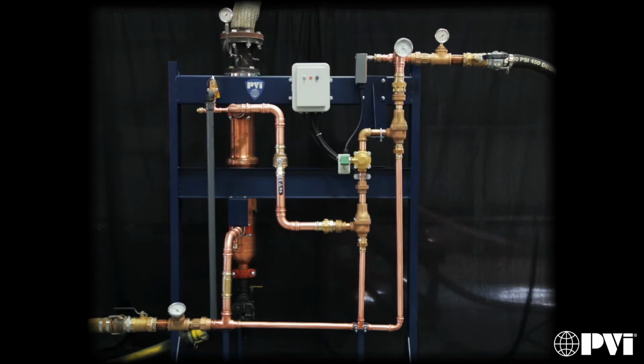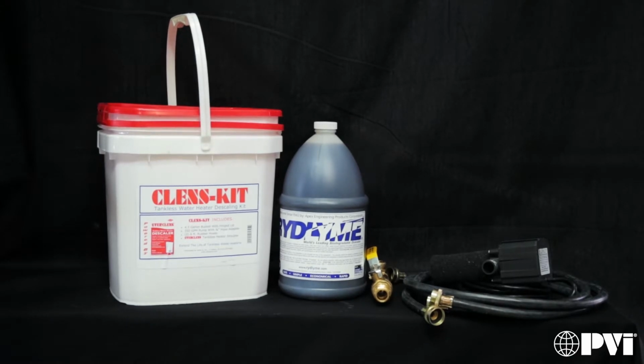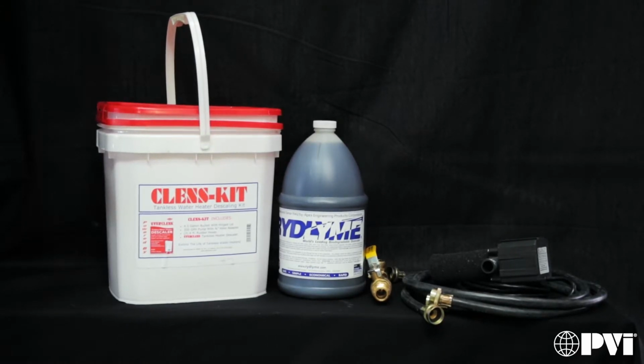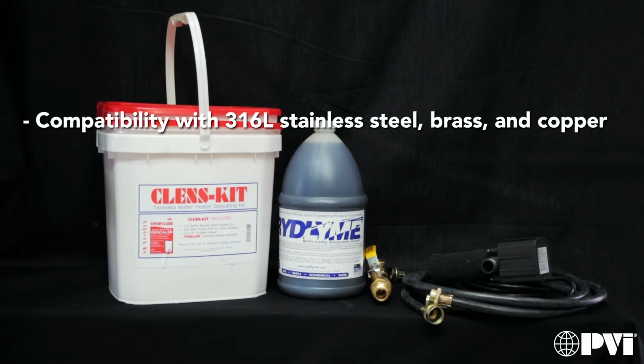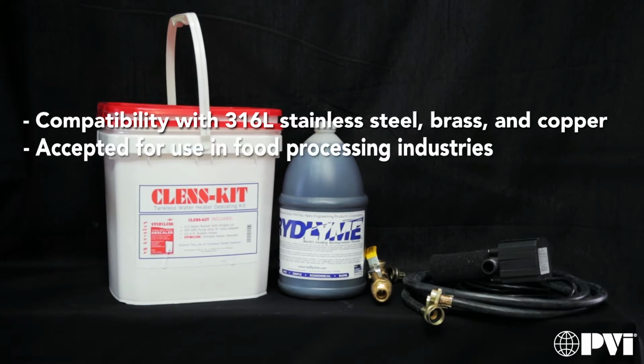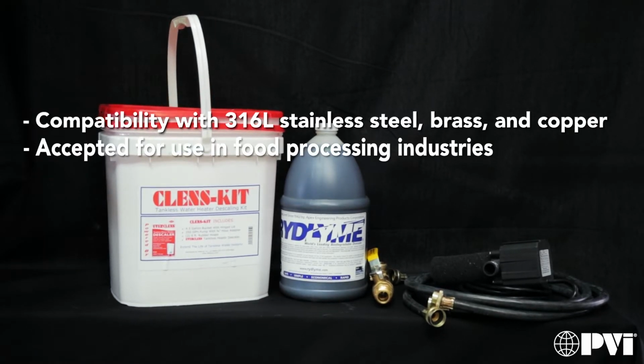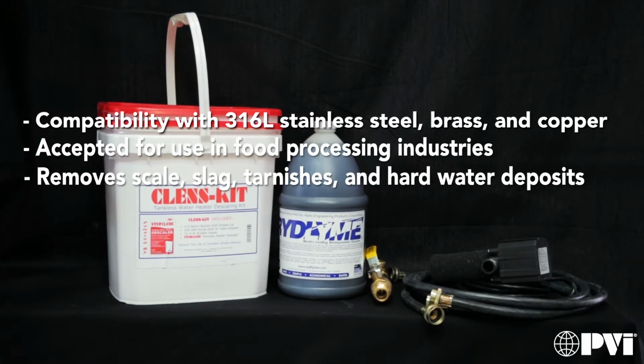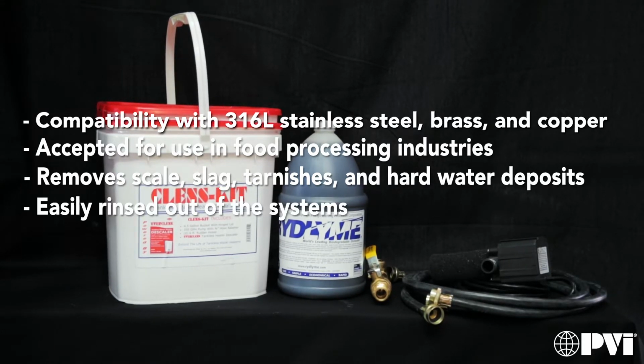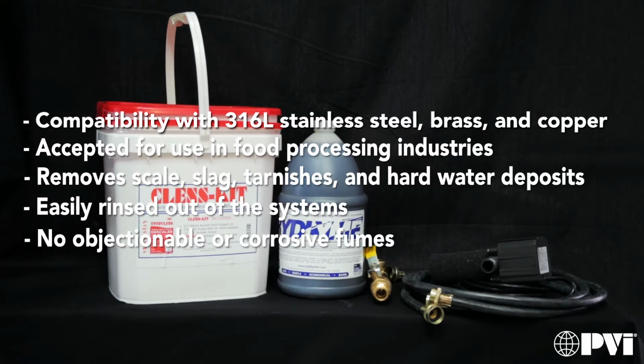long-term frequency required. Loss of heat transfer is an indication of water-side scale buildup that would require more frequent cleaning cycles. In all cases, the heat exchanger should be cleaned on the stand and not removed unless determined to be necessary. The cleaning solutions are available at plumbing supply businesses that carry chemical cleaning agents for heat exchangers or tubing and piping applications. As a guideline to selecting the right cleaning solutions, check for the following product properties: compatibility with 316L stainless steel, brass, and copper, accepted for use in food processing industries, removes scale, slag, tarnishes, and hard water deposits, easily rinsed out of the systems, no objectionable or corrosive fumes.